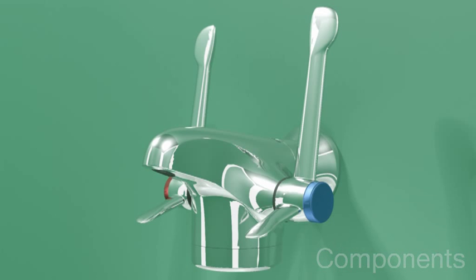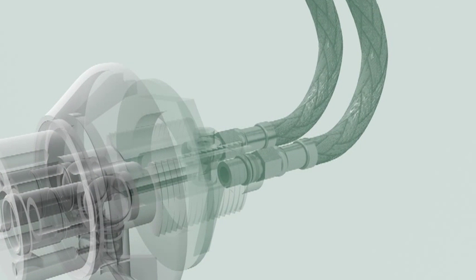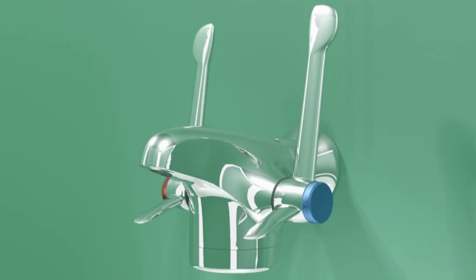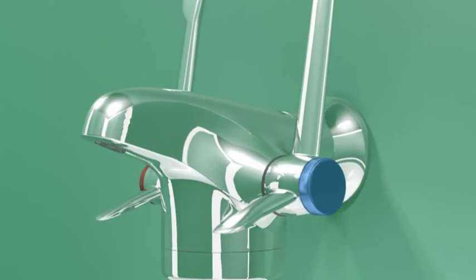Installation and maintenance of the OptiTherm is extremely easy. The spigot can be supplied in advance of the tap body if a phased installation is required. Connections are made with soft PEX braided hoses or by compression fitting to copper pipe. When any maintenance is due, there is no need for access behind the wall panel. Isolation of the water supplies and access to the strainers, check valves and internal thermostatic mechanism is easily achieved from within the room or ward.